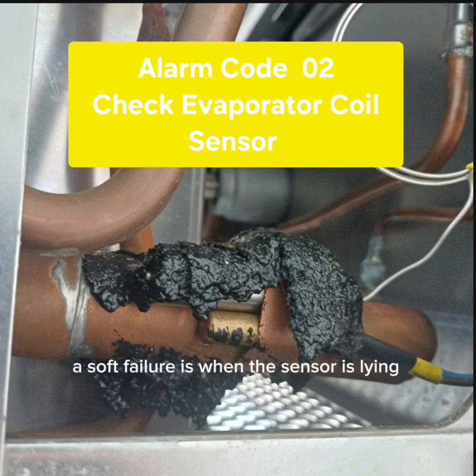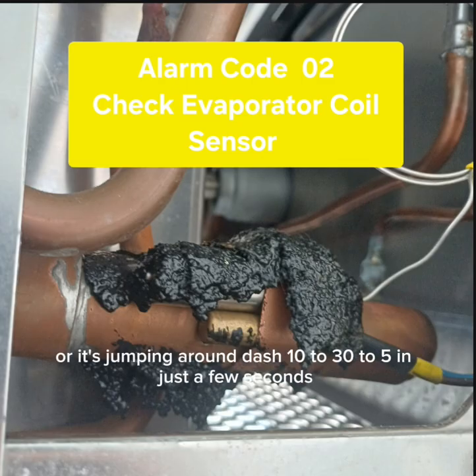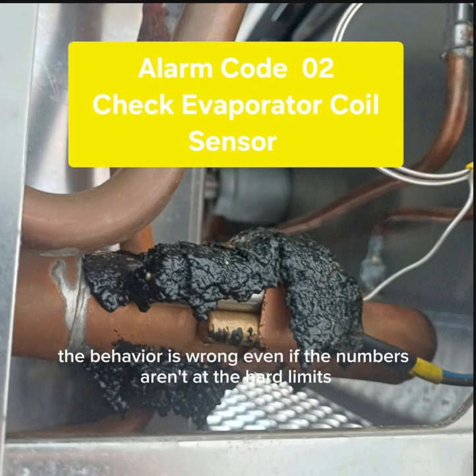A soft failure is when the sensor is lying, but the lie is plausible. It's subtle. So it's still within the range. Exactly. It's not reading 200 degrees. Maybe it's reading 40 degrees when it should be 10. Or it's jumping around, dash, 10, 30, 5 in just a few seconds. The behavior is wrong, even if the numbers aren't at the hard limits.